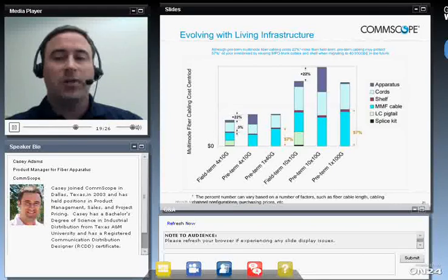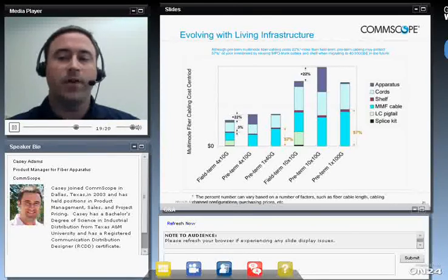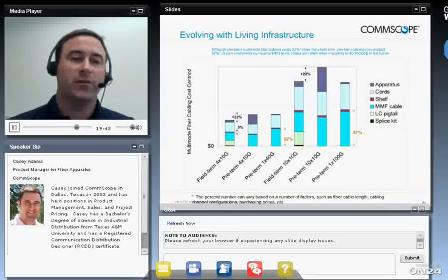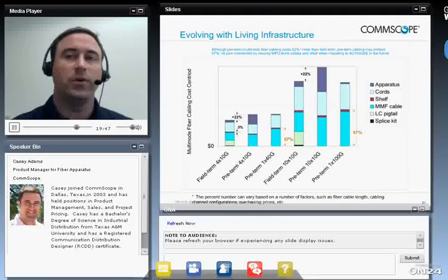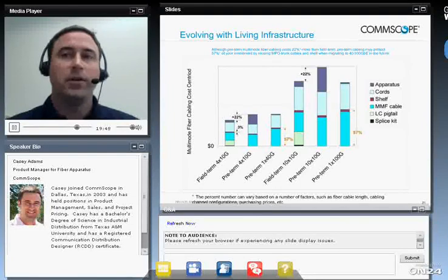A study that CommScope conducted regarding the cost of the modular system versus the cost of a fiber field term fiber system showed that while the upfront cost of a pre-terminated fiber solution may be higher, the pre-term systems may protect 57% of your investment by reusing MPO trunk cables and supporting apparatus for migration from 10 gig to 100 gig.